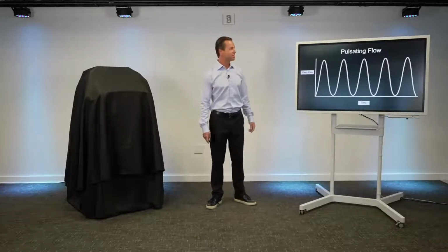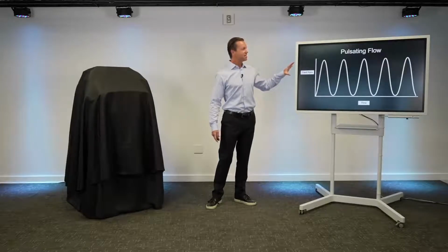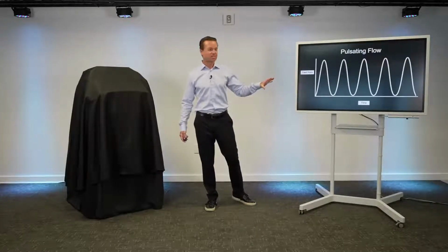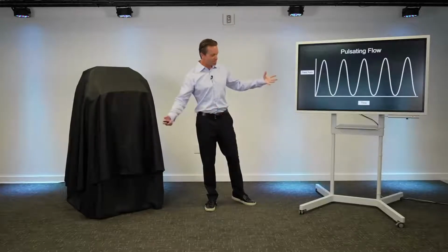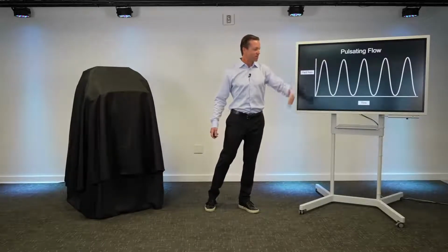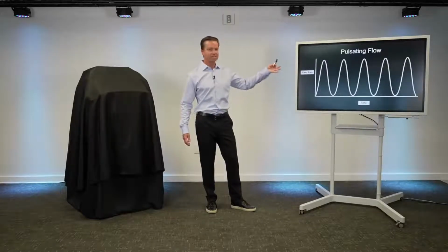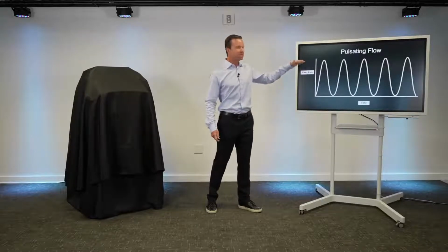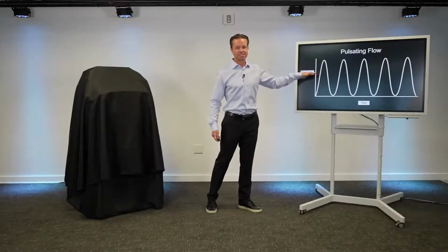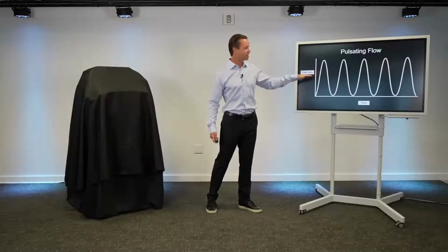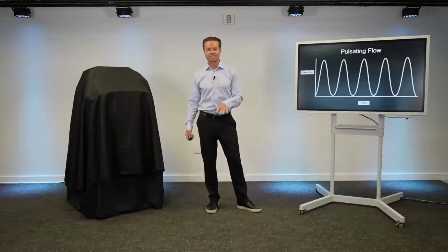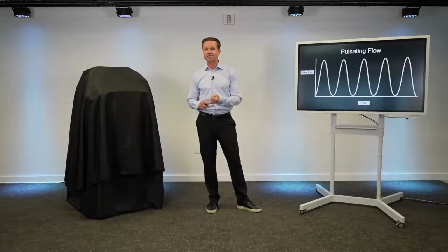So the next issue that we saw in the field when we looked at the chemical feed, high volume chemical feed solutions, is extreme pulsating flow. Okay, imagine this being a big peristaltic pump pumping above 5 gallons per minute. You're going to have these extreme pulsations, or this could be a diaphragm pump, right? But these big pulsations are a pain to deal with. It's always a pain to deal with pulsating flow, but they can wreak havoc on your system. Your plumbing, your instrumentation can easily get damaged with this pulsation.